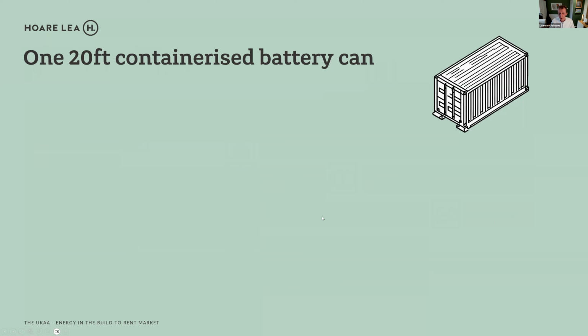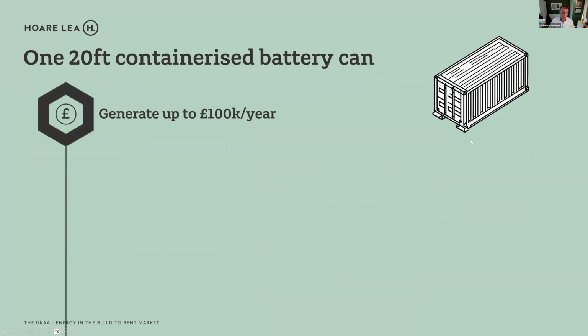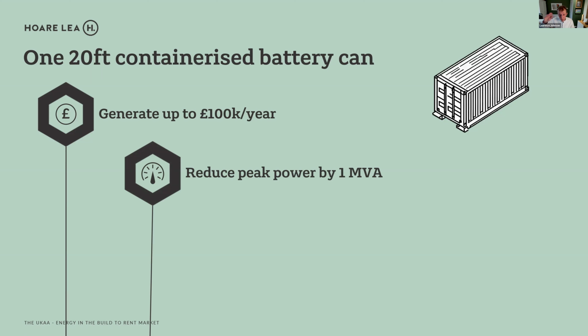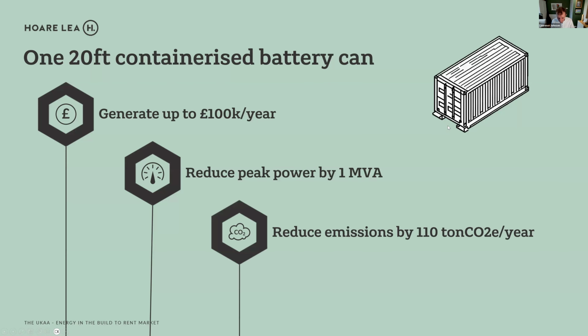Just to give you a flavor of what I mean: a box full of batteries, typical of what you might buy now - and battery technology is changing rapidly, people might be frightened by this, but it really is going through lightning changes at the moment with much better technologies coming through. A typical 20-foot shipping container, which could be found space for, might take up a couple of car park spaces, can generate up to £100,000 a year in revenue. It could reduce your peak consumption by up to a megawatt at some point during the day - not for long periods, but it could do that. And it can reduce your emissions by 110 tons of CO2 a year by storing energy when it's low in carbon and playing it back when it's high.